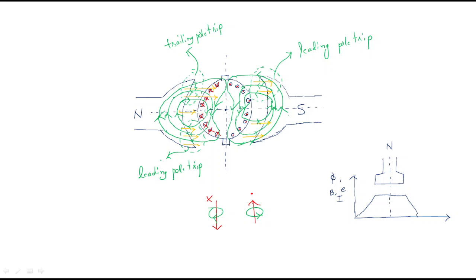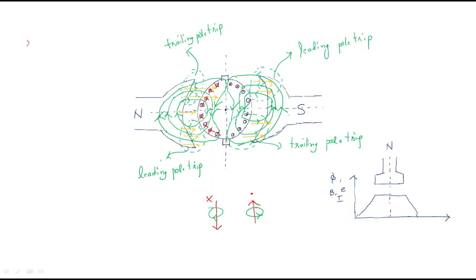At the trailing pole tip, both fluxes are added together. At the leading pole tip, the fluxes are in opposite directions. At the leading pole tip, the main flux decreases because both are opposite to each other, and this process is called demagnetization.